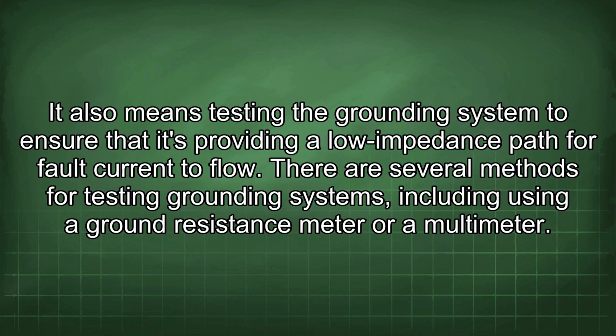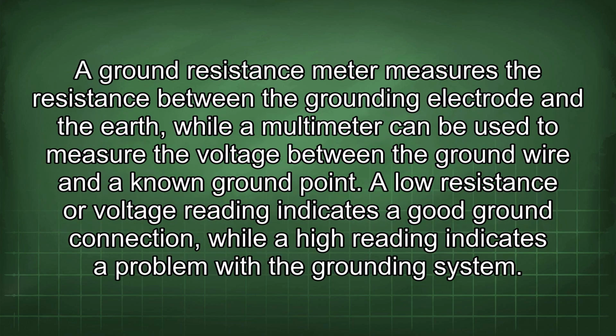It also means testing the grounding system to ensure that it is providing a low impedance path for fault current to flow. There are several methods for testing grounding systems, including using a ground resistance meter or a multimeter. A ground resistance meter measures the resistance between the grounding electrode and the earth, while a multimeter can be used to measure the voltage between the ground wire and a known ground point.